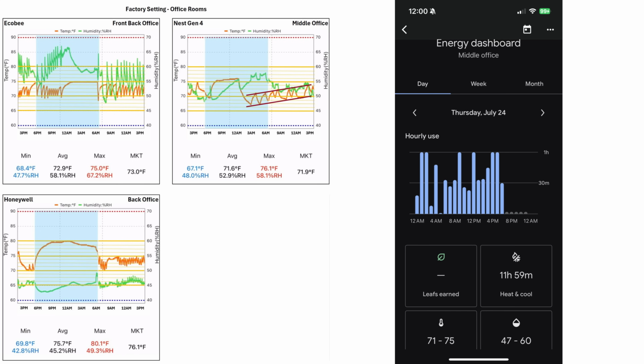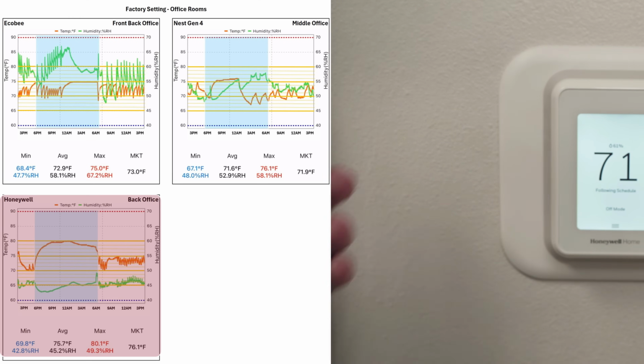And the last thing I want to point out is the run times. It's pretty common for this to turn on for a full hour at a time, then turn back off for about a full hour. And if you look at the Ecobee over here, it's able to turn on, satisfy the room, and turn right back off. So what that's telling me is we either have an undersized unit, which I know is not the case, so that would mean that we have airflow issues in this room. I'm just trying to point out that the long run times is not the fault of the Nest thermostat. Now let's jump over to our Honeywell thermostat.